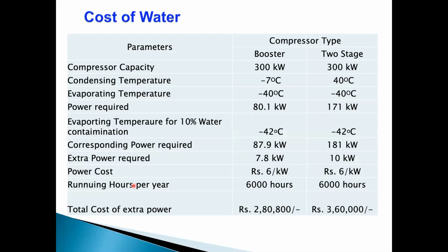What is the cost? This is a case study which we have done and installed. Typically you have a booster compressor of 300 kilowatts in a high stage booster system, which is at -40. Because of the water, instead of -40 you're operating at -42.